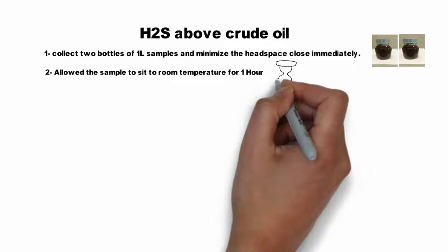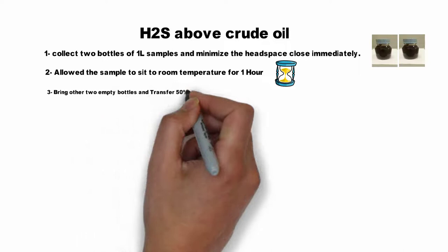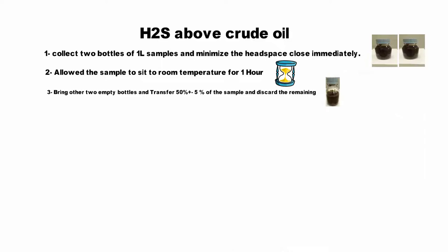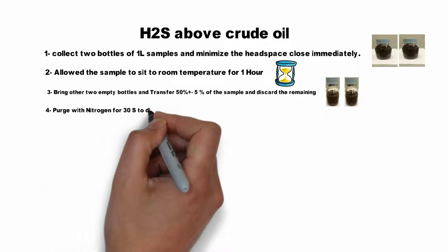Bring two other empty bottles and transfer 50% plus or minus 5% of the sample, then discard the remaining. Purge with nitrogen for 30 seconds to displace the air and water vapor, then close the sample bottle.